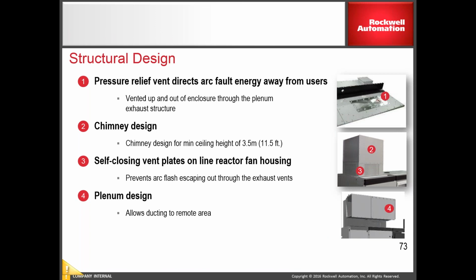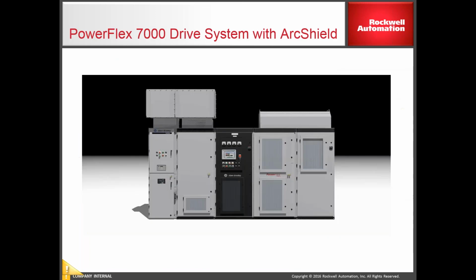There's also a pressure relief vent on the top of the unit. This is the chimney design that also includes the self-closing vents. And then the plenum, which you can direct out the side of the building. So if there's a fault, any gases will be expelled outside of the building.